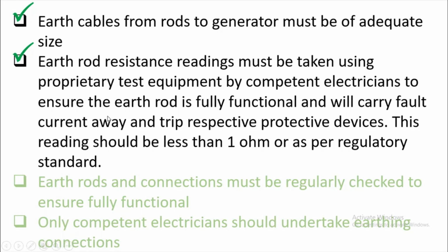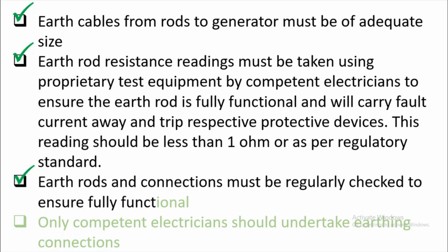He can assure that this earth rod is fully functional and it will carry the fault current away. Okay, so the reading should be less than 1 ohm. Earth rods and connections must be regularly checked to ensure they are fully functional.